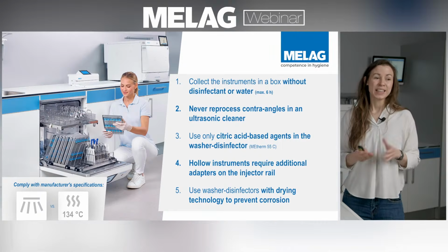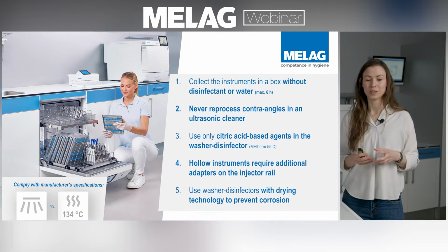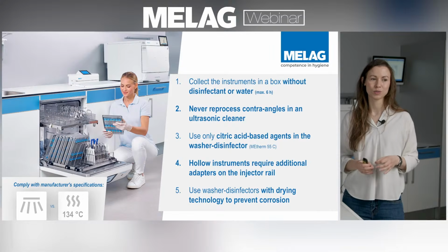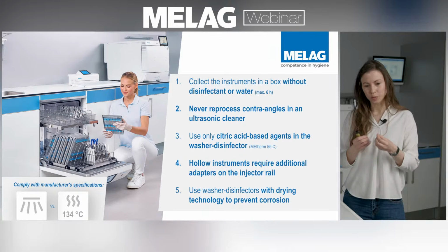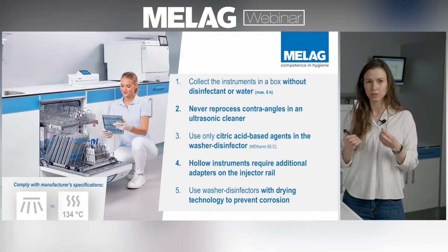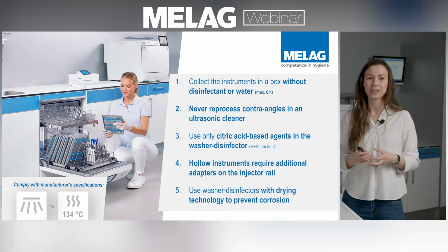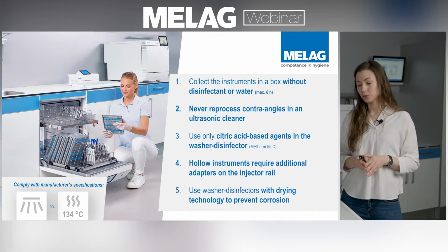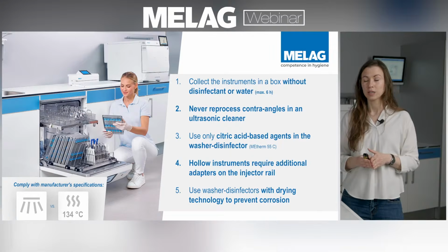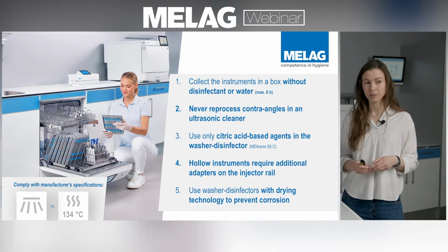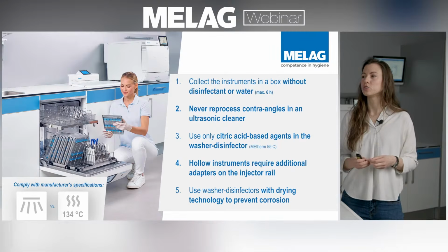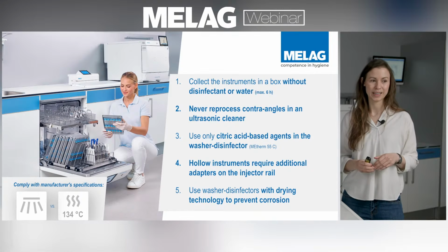The second thing to be really aware of: never put your handpieces into an ultrasonic cleaner, because the vibration will damage the inside parts of your handpieces, for example the ball bearings. That is something you must never do. And thirdly, when you use, for example, a thermal disinfector with an active cleaning agent, always make sure that it is citric acid based, because other agents might be a little too aggressive. Therefore, always check and only use citric acid based agents.